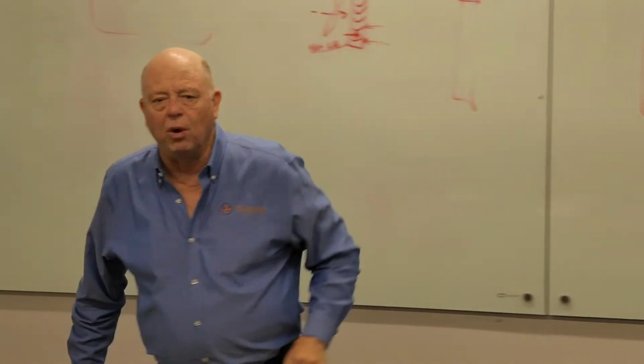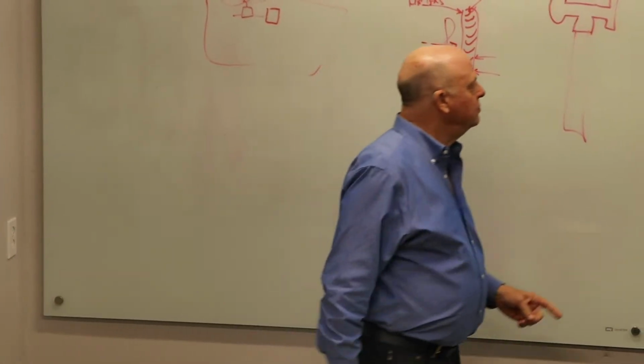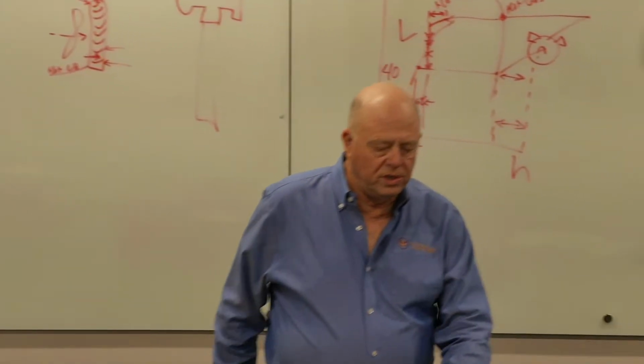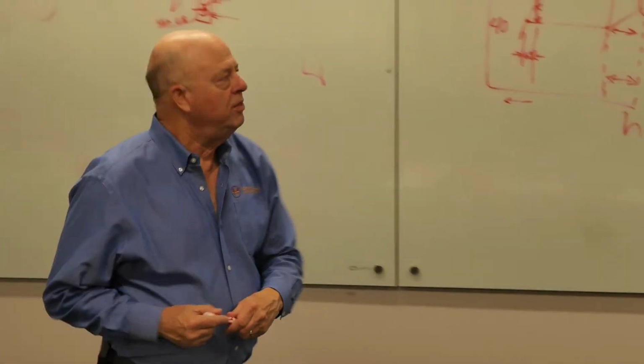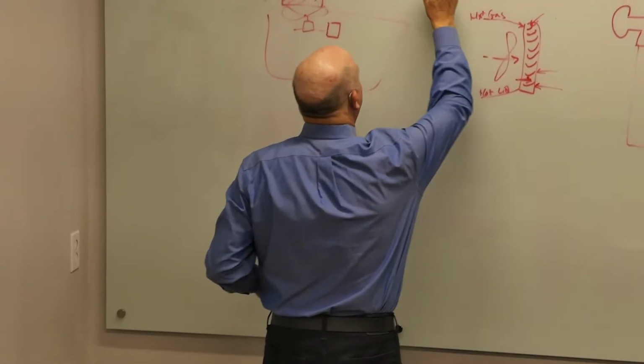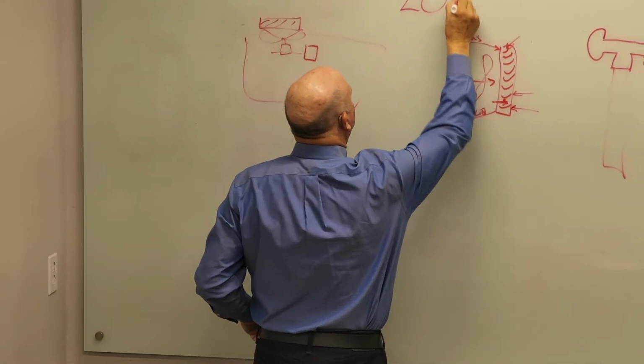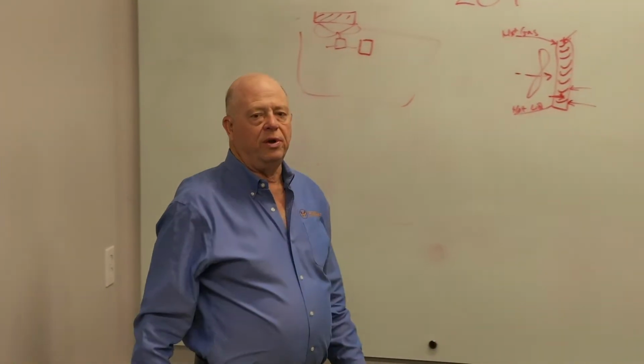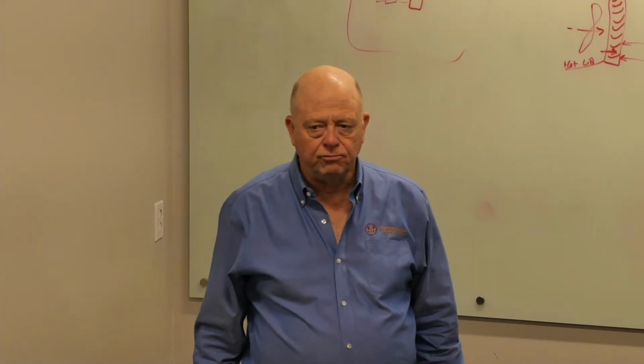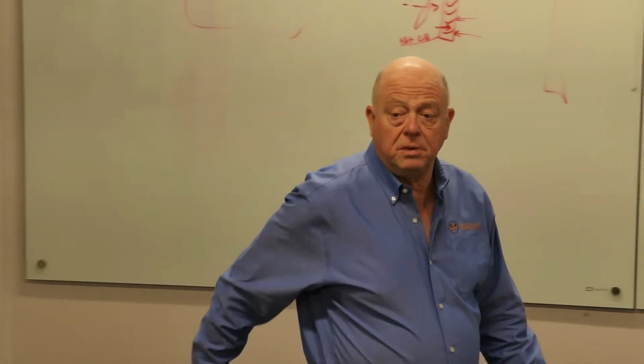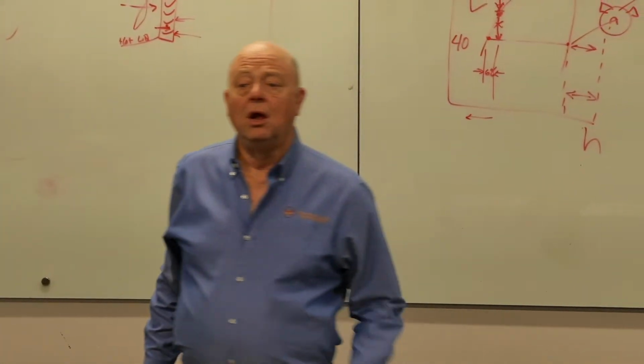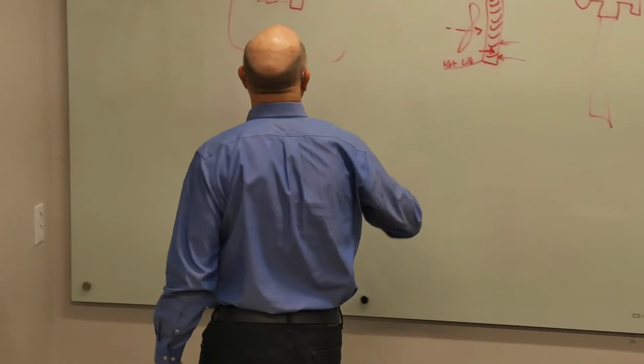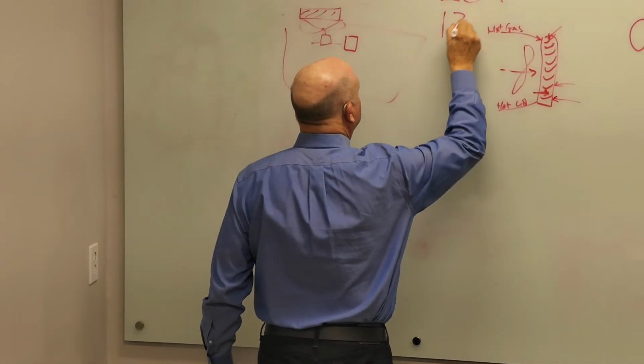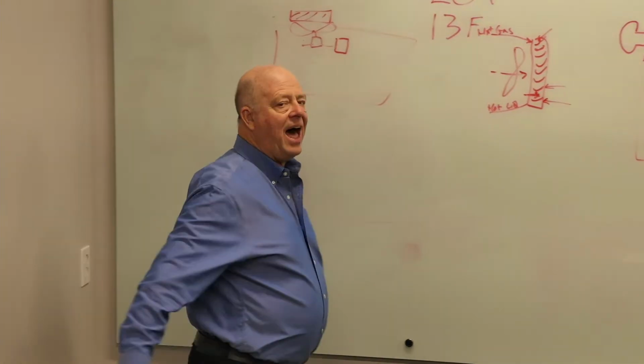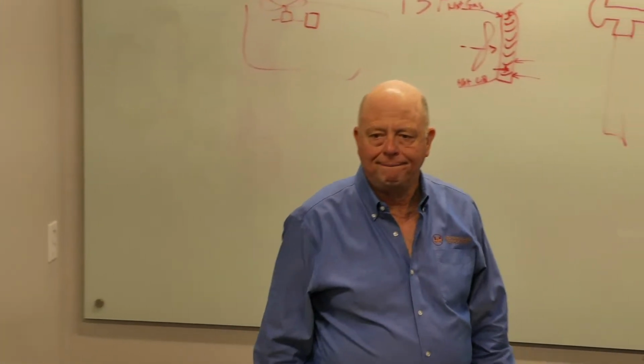But to be safe, what we ended up deciding is, you will usually see that the typical recommendation from the manufacturers is they want at least 20 degrees of superheat. That's because they have warranty responsibility and they're trying to cover themselves. What most service technicians out in the field will charge to is more like that, or maybe a little bit more.